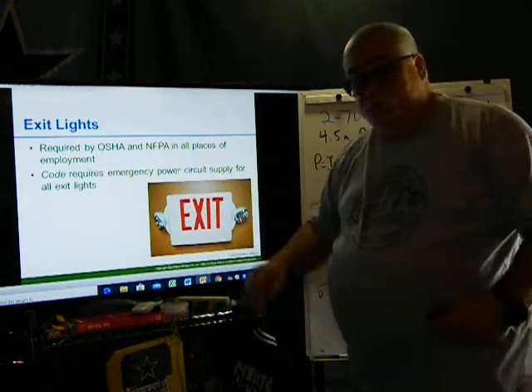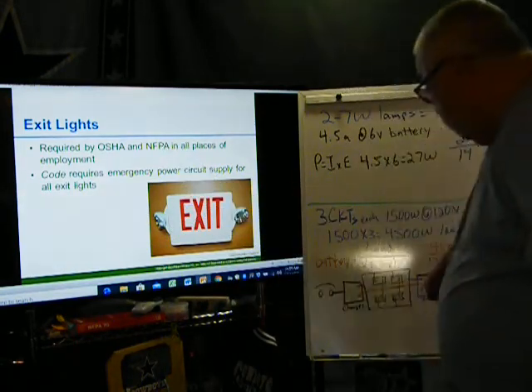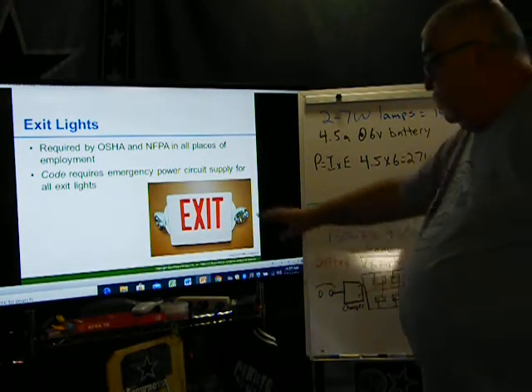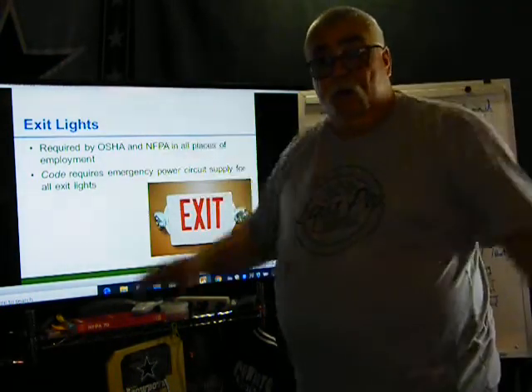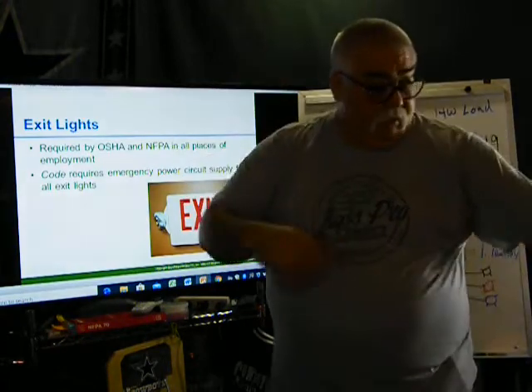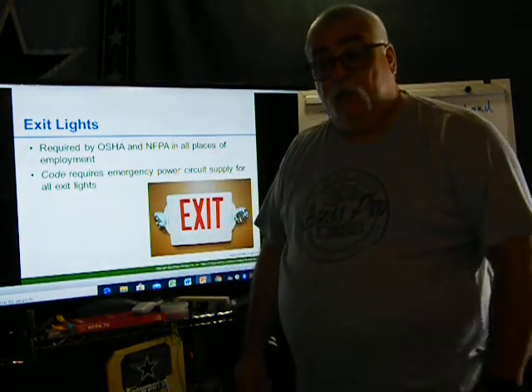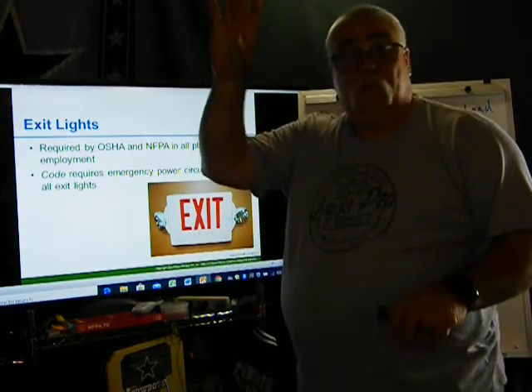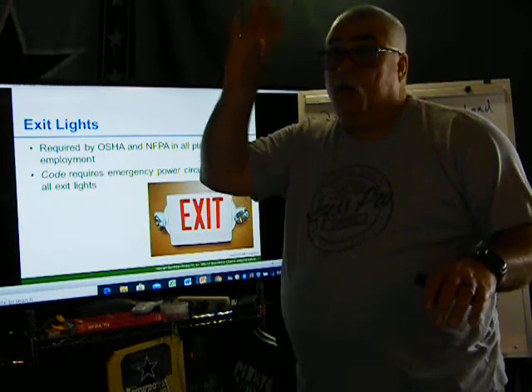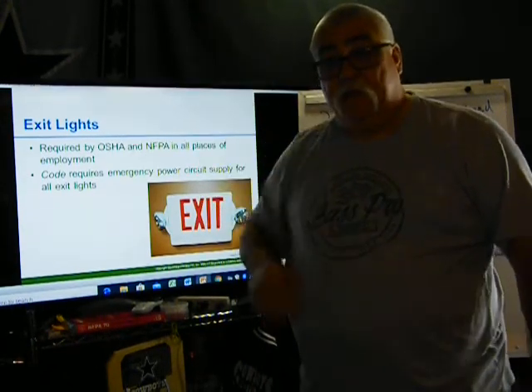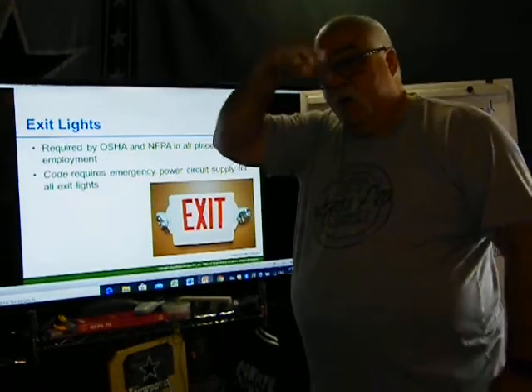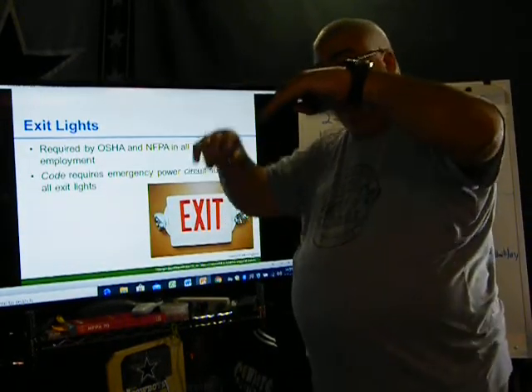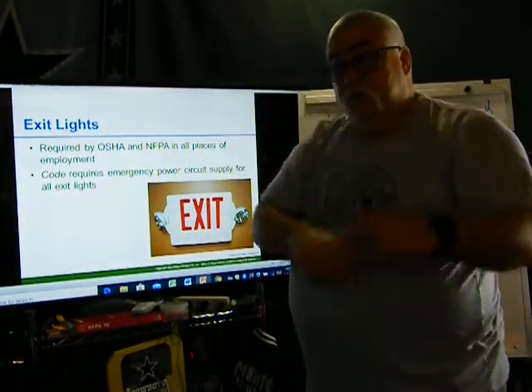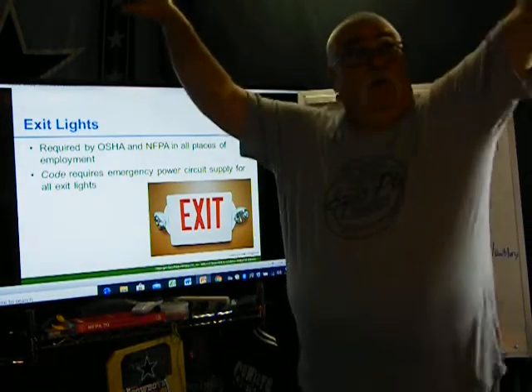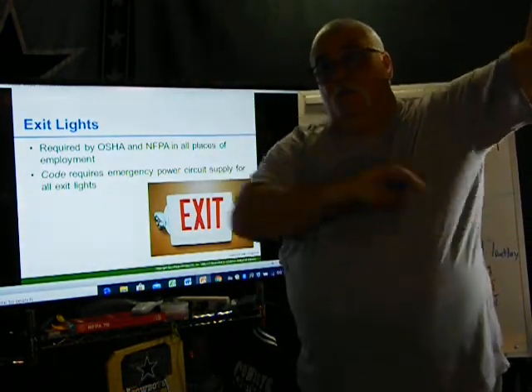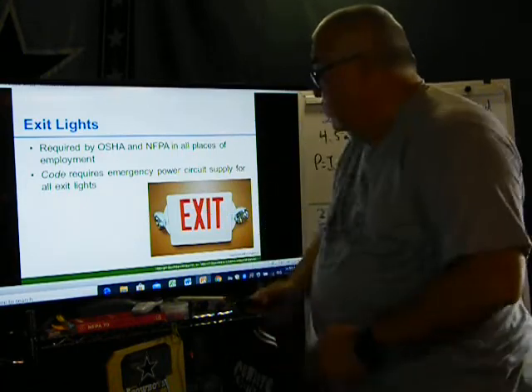So what does this do? This affords you not having to worry about going back and having to wire batteries in. So you put these in your hallway, just like that emergency bug light that I have. That one you would put in the stairwell. Guess what? You get one lighting up the stairwell, one lighting down the stairwell. So when people exit, you have them at each landing. Your stairwell goes down this way, turns around, goes back down this way. So you've got one here, one at the top, one at the bottom. So you're lighting up everything as you go.